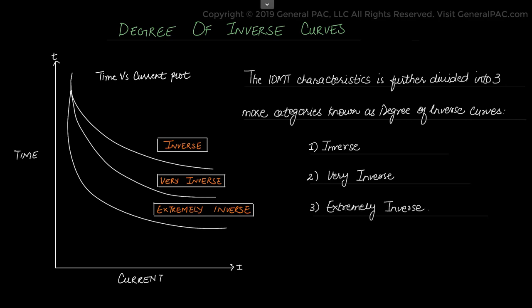An overcurrent IDMT relay may be programmed to set to work with any of these three degrees depending on the specialized type of protection that is required. Usually an overcurrent relay is used for motor protection against overloads and short circuits in stator windings of the motor. It's also used in sub-transmission lines where the cost of distance relaying cannot be justified and distribution system protection.